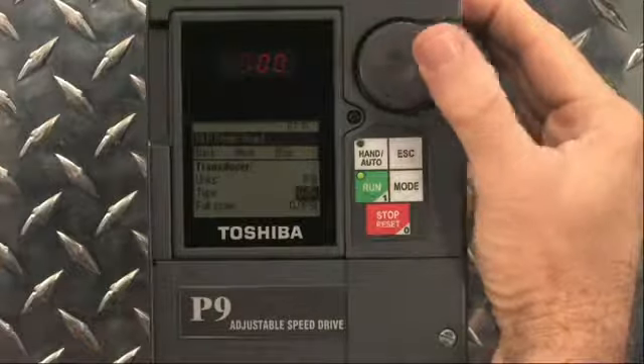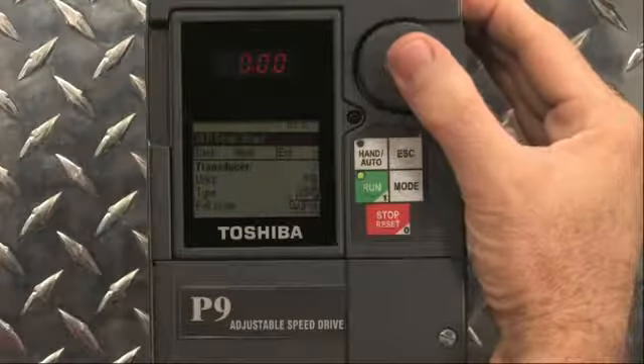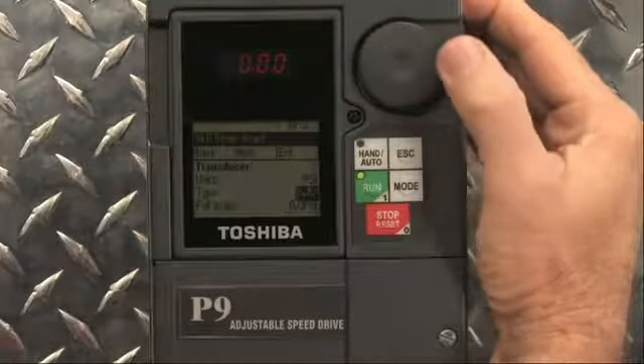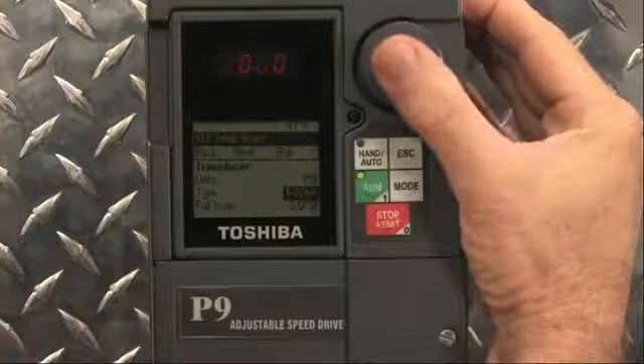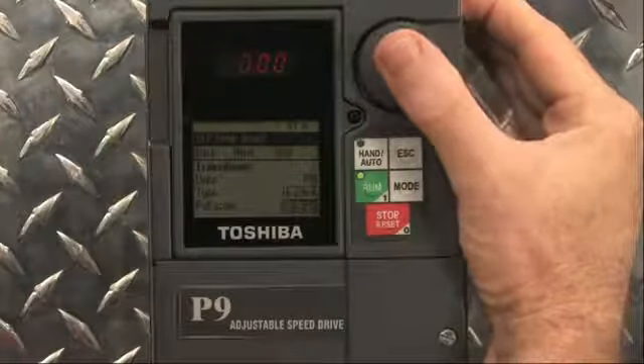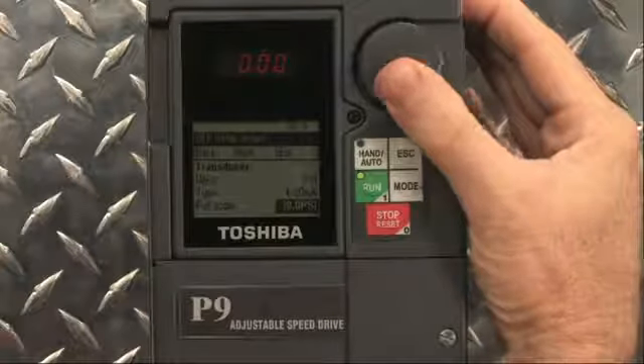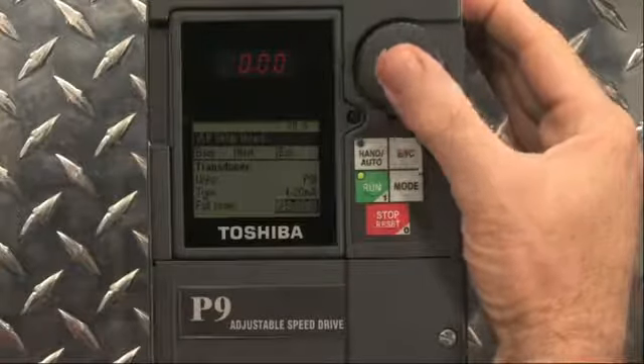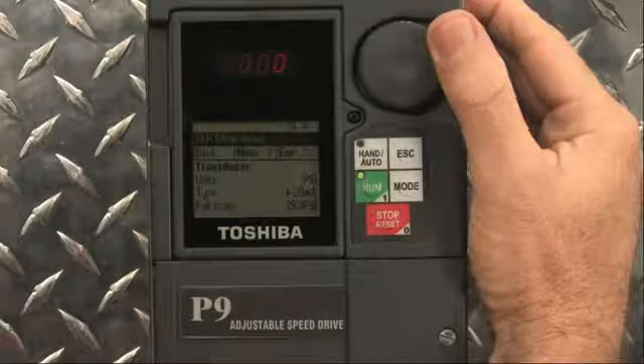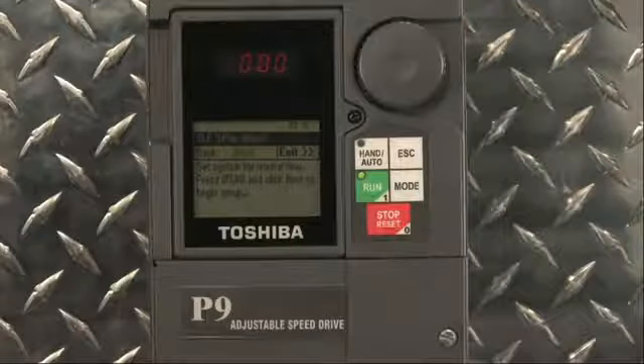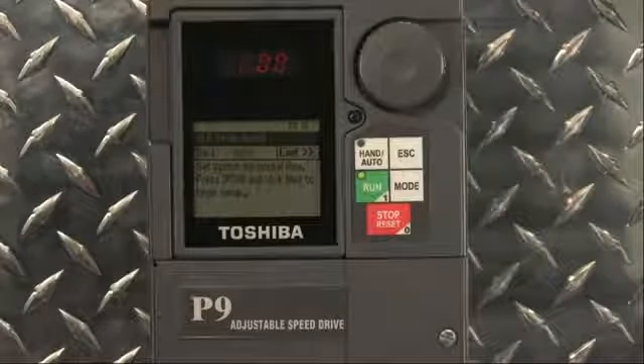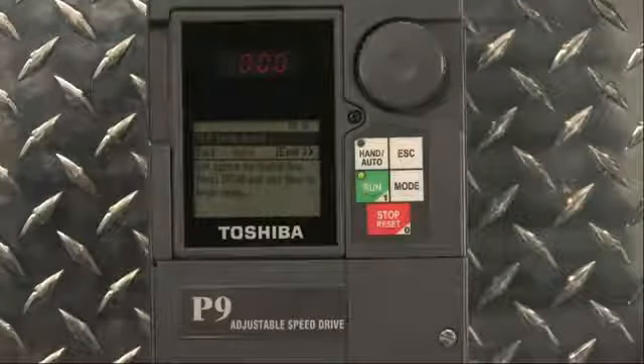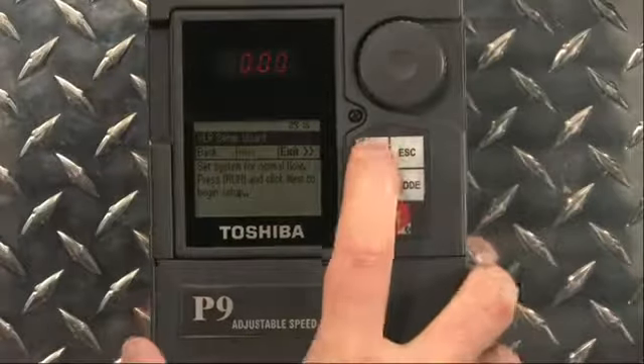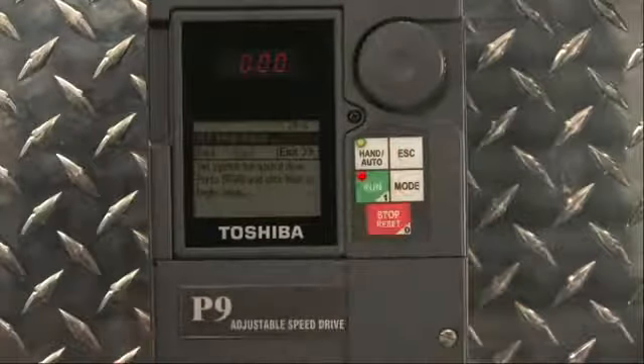The next thing we need to select is full scale, or the range of the transducer. This transducer has a 0 to 30 psi range, so let's rotate the encoder to indicate 30 psi. With this information now entered, select Next and press Enter. The following screen prompts us to set the system for normal flow. For the VLP setup, normal flow means avoiding deadheading the pump or causing cavitation. Then, ensuring the P9 is in hand mode, press the Run button. After allowing the pump to start and accelerate up to full speed, scroll to Next and press Enter.